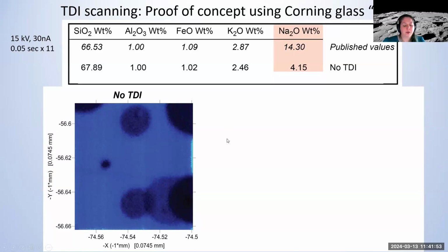Likewise, I don't trust the detector. When I actually look at the detectors, oftentimes the first second is not always correctly read out. I talked to JEOL about that. They know about it. I actually found that the JEOL software seems to clip the first second often, which is not great.